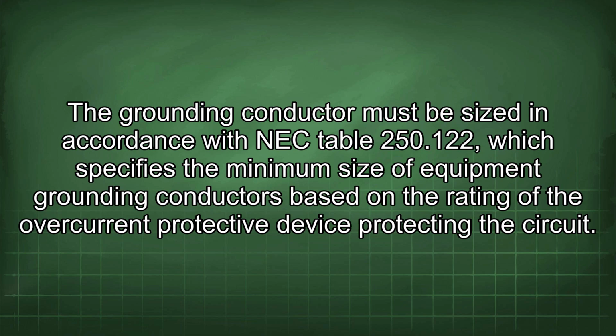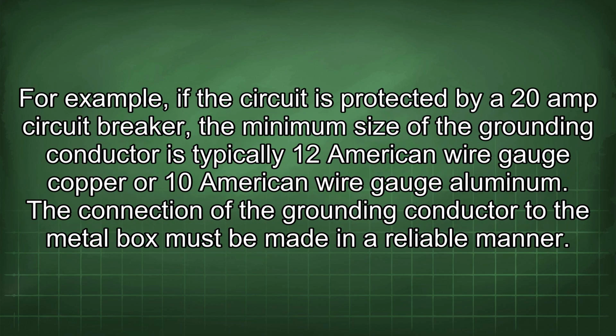The grounding conductor must be sized in accordance with NEC Table 250.122, which specifies the minimum size of equipment grounding conductors based on the rating of the overcurrent protective device protecting the circuit. For example, if the circuit is protected by a 20 amp circuit breaker, the minimum size of the grounding conductor is typically 12 American wire gauge copper or 10 American wire gauge aluminum.